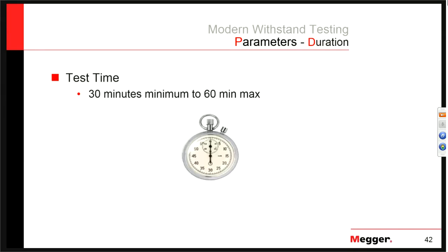Q&A: Is there any difference between a 50/60 Hz withstand test and VLF in terms of accelerating aging conditions? Yes, there is, but at the voltage levels we're talking about — about 2 times operating voltage for maintenance test values — 50/60 Hz is actually very similar to VLF in terms of growing water trees. As you vary voltage above or below that target, there becomes a little difference, but at our target voltages they're actually very similar.